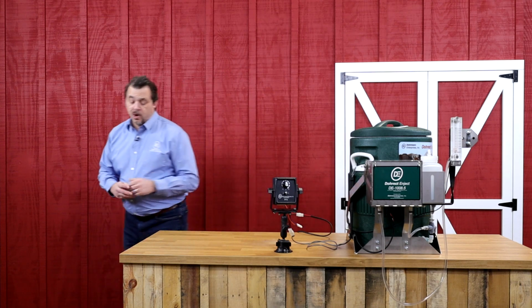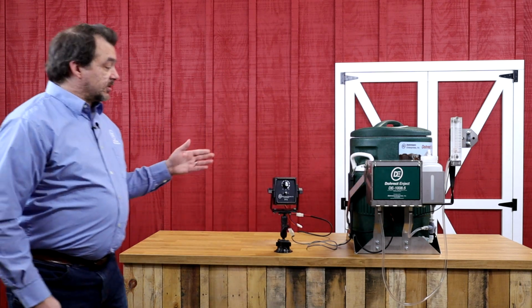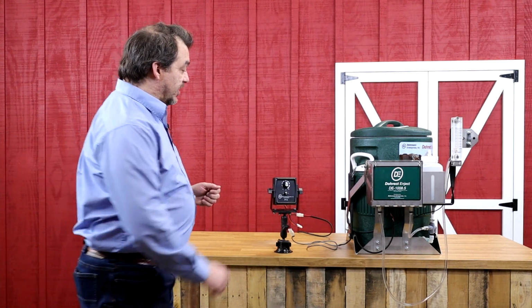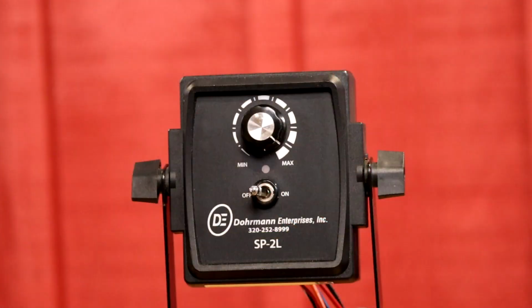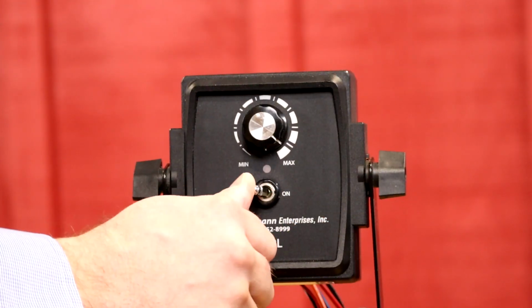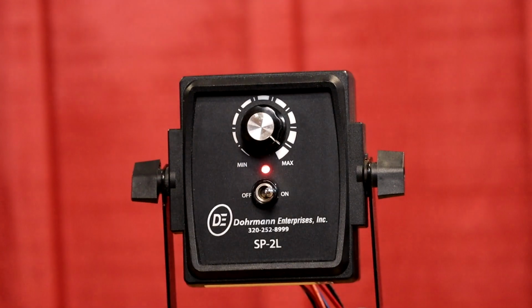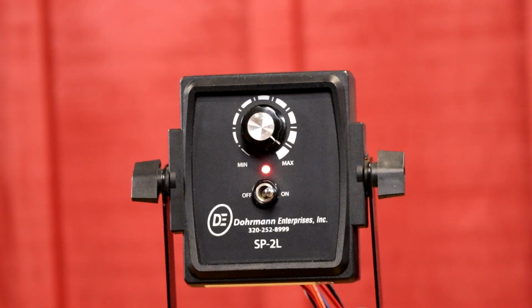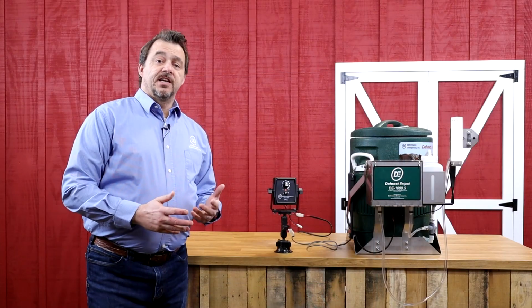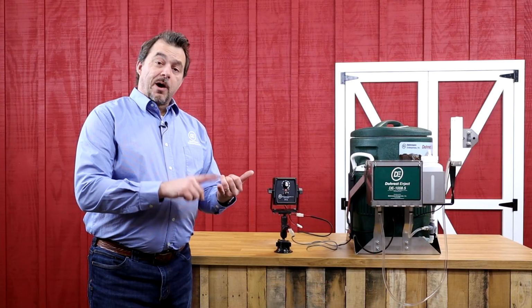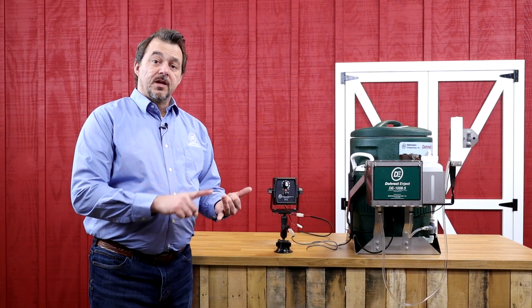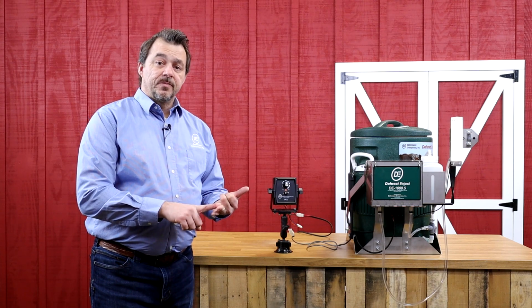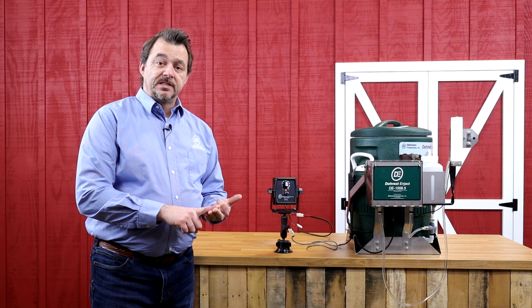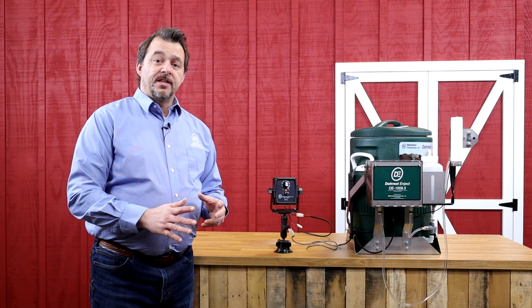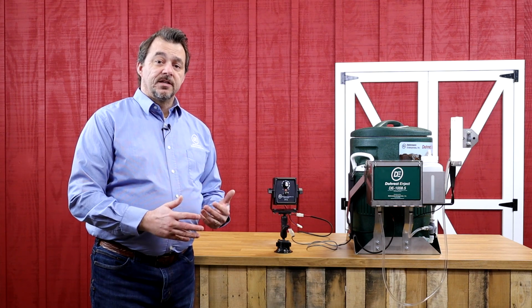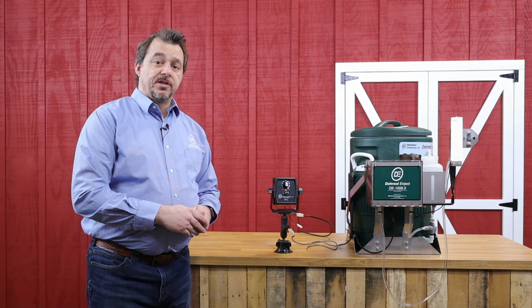So the first thing we're going to want to take a look at is to make sure that the red light on the controller turns on. With power to your controller, we want to turn that switch on. If we see that red light, that gives us an indication that we have power to the controller, that it is wired correctly, and that it's hooked up to a 12-volt system. In the event any of those things are not correct, that red LED light is not going to turn on.